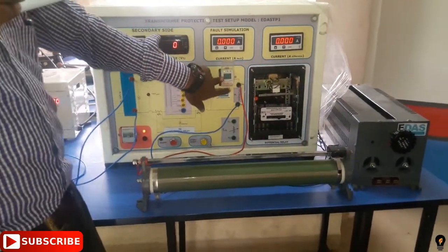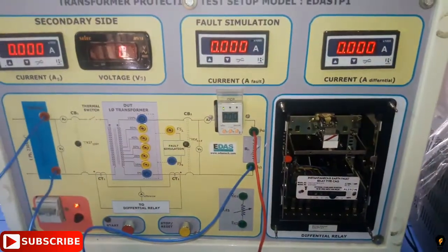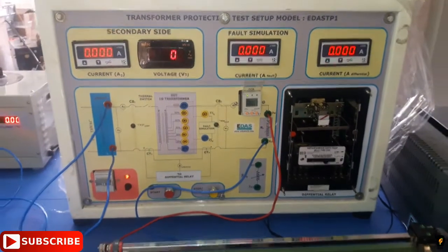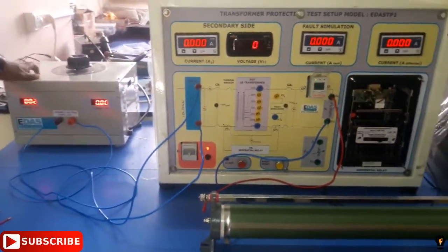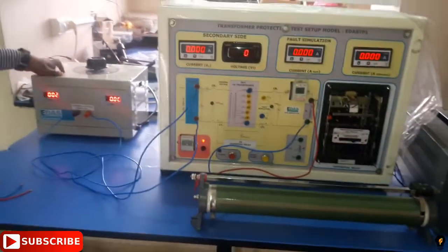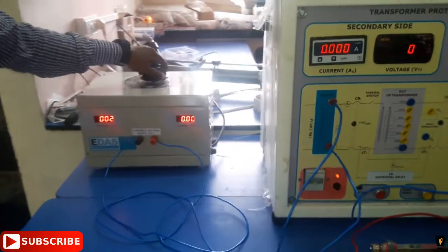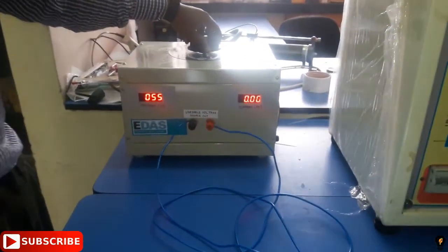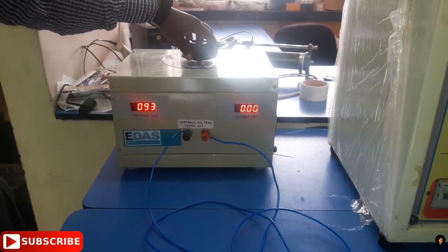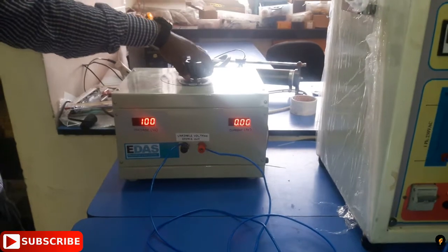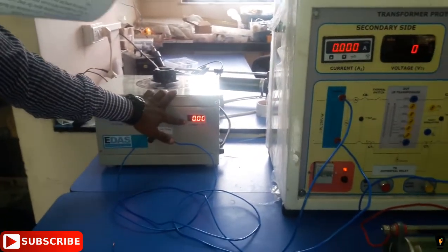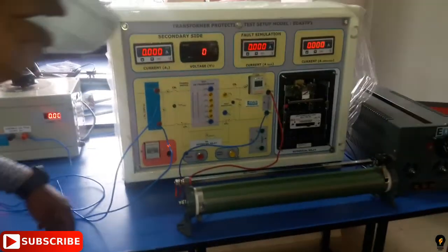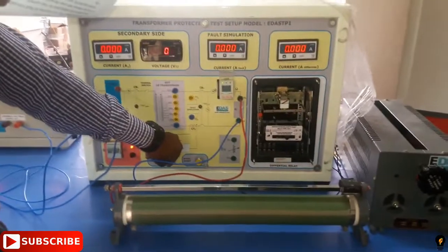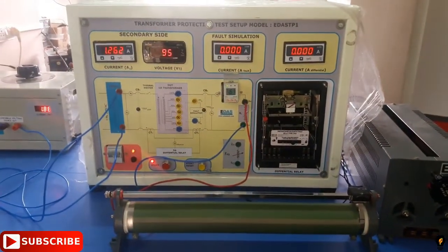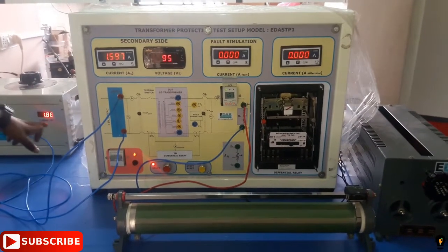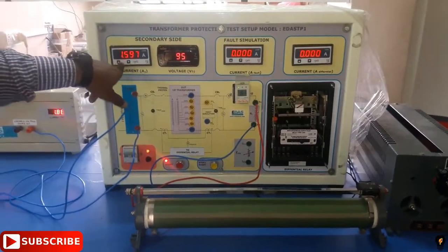Overcurrent relay is set to be at 3 ampere. Do not set the overcurrent relay more than 4 amperes. Now set the voltage at 100 volt by moving the source knob clockwise. Now you can see the current is 0. Press the start button to observe the current at source as well as the secondary current of the TPTS. This is the source current and the secondary current of the TPTS.